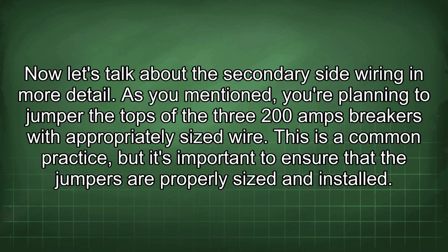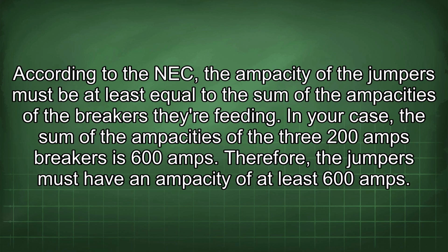Now let's talk about the secondary side wiring in more detail. As you mentioned, you're planning to jumper the tops of the three 200 amp breakers with appropriately sized wire. This is a common practice, but it's important to ensure that the jumpers are properly sized and installed. According to the NEC, the ampacity of the jumpers must be at least equal to the sum of the ampacities of the breakers they are feeding.